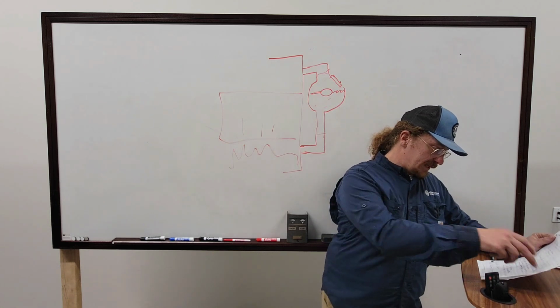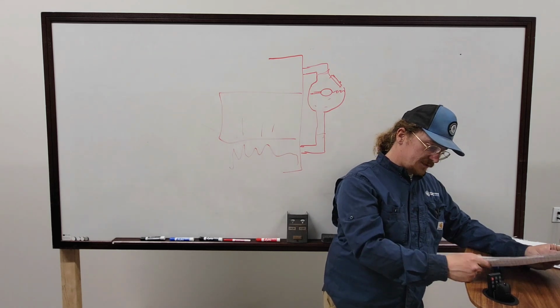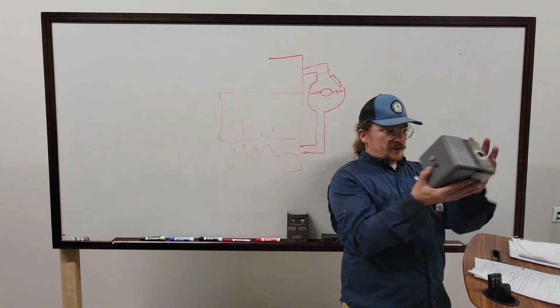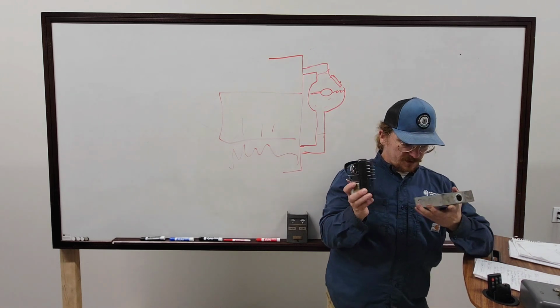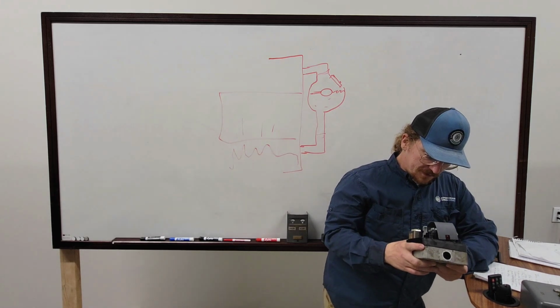The only thing that makes a flame sensor is that it's got a silicon coating on it, but it's just a piece of stainless steel. You have controllers, some sort of burner controller. This is where all the sequence of operations happens. This is the brains of the operation, so to speak. It's going to see that you have safeties met.